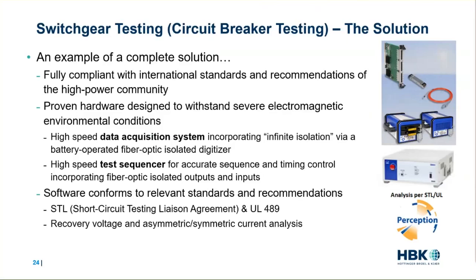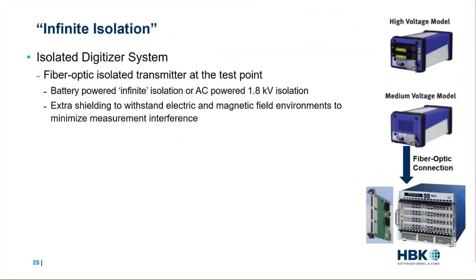Now, the software even conforms to relevant standards and recommendations, including STL, the Short Circuit Testing Liaison Agreement, and UL 489. There's also recovery voltage and asymmetric and symmetric current analysis. So first, let's start with the hardware. In this example, we have an isolated digitizer system, which starts with a fiber optic isolated transmitter at the test point. Now, for near infinite isolation, you can use a battery powered unit. However, for the AC powered style, you've got a 1.8 kilovolt isolation capability.